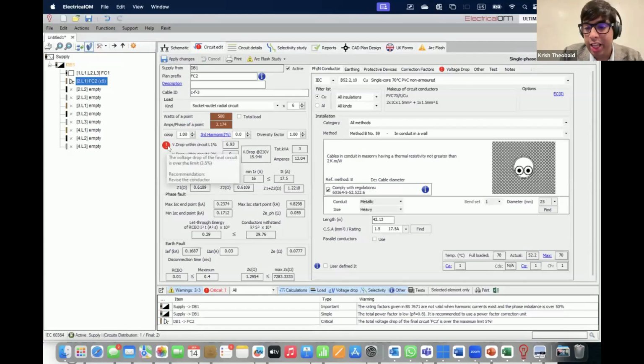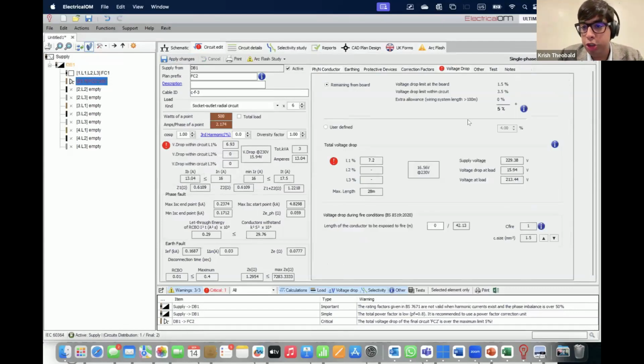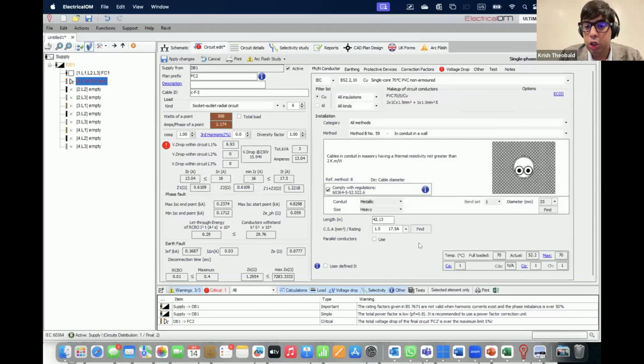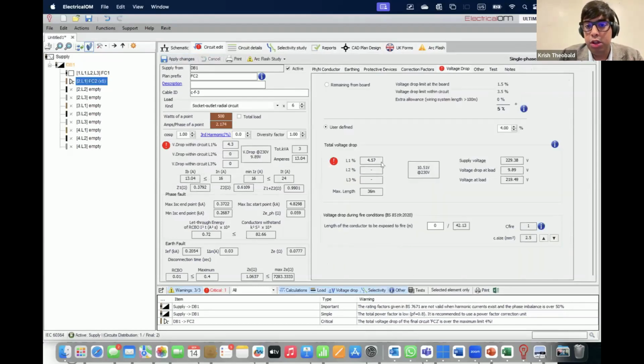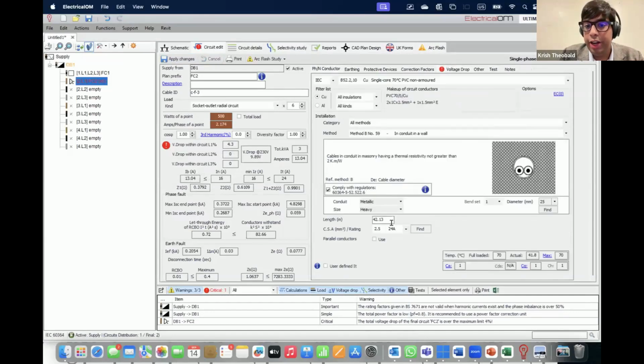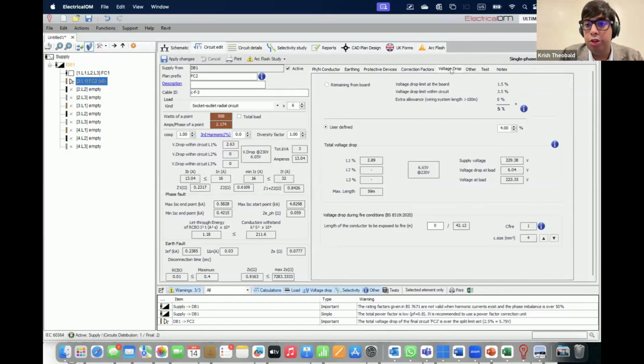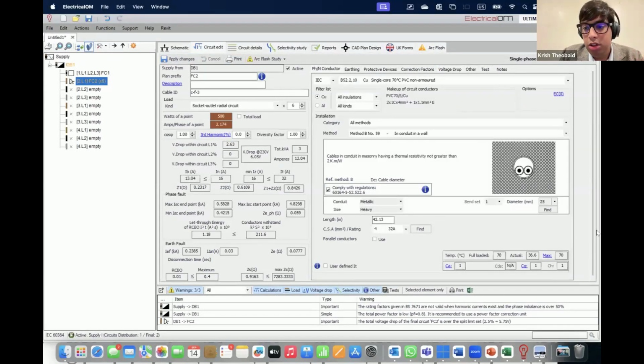However, it's flagging a voltage drop issue. So if I go to voltage drop, I've only allowed 3.5% voltage drop on this. I can obviously user define it, say I want 4% voltage drop, but I'm actually getting 7.2% voltage drop. If I increase this from 1.5 to 2.5, I'm still getting 4.57, which is relatively high. If I increase this now to 4, the voltage drop issue is going away. So that's how it actually works.